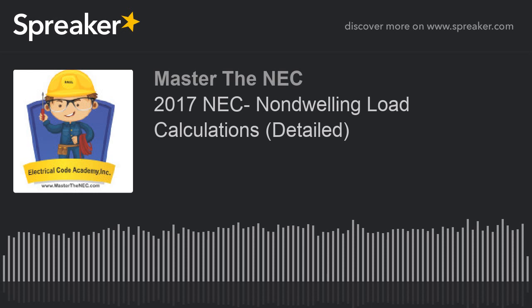The one thing it also reminds us that you should be aware of in 220.56, which most people won't pay attention to, is that in a kitchen you might have two larger pieces of equipment. And when you're doing a feeder or service calculation, you're applying all these things that we're doing for the general lighting and everything, the load that you come out after you apply all these demands, at the end of the day, the value for this load calculation for the service or feeder can't be less than the two largest pieces of kitchen equipment. Okay, and I think that's probably going to be rare, but you just have to remember that it can't be less.